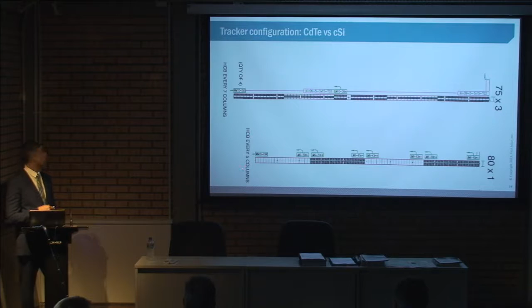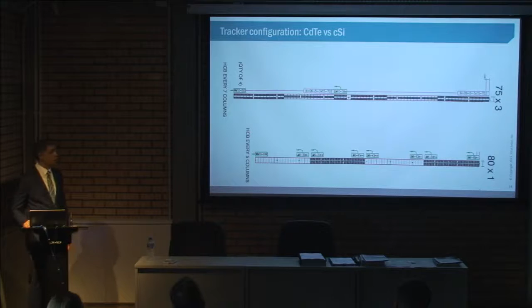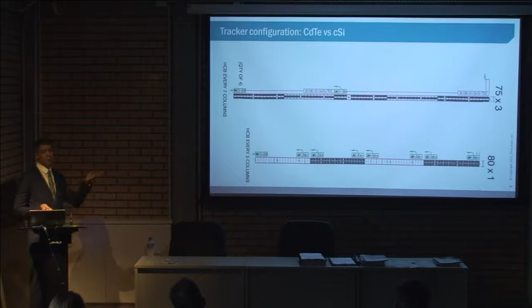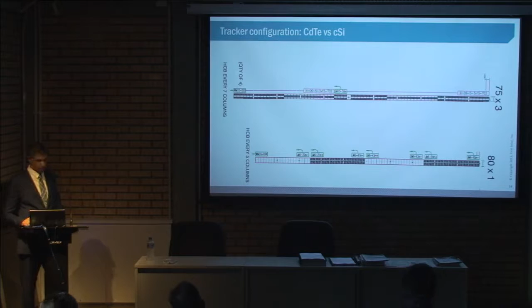Here again are the 2 trackers. I wanted to point out that this configuration can be optimized - you can use a harness for 2 series, so you'd have 4 conductors at the end of the tracker, same as here. The delta in cost, labor, and materials in this case was very small, so I didn't bother calculating it, especially since the difference between the savings and additional cost is so big. So there are still important savings by going with 1,500 volts.